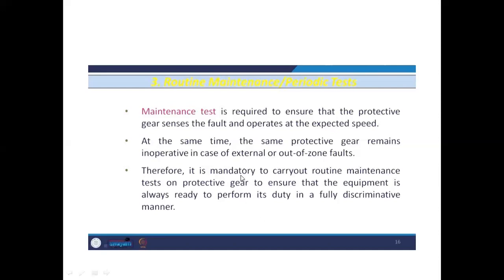Okay, so it is mandatory to carry out routine maintenance tests on protective gear to ensure that the equipment is always ready to perform its duty in a fully discriminative manner. Fully discriminative manner, I have discussed this point, means that the relay should be able to discriminate between the healthy portion and the faulty portion of the circuit.